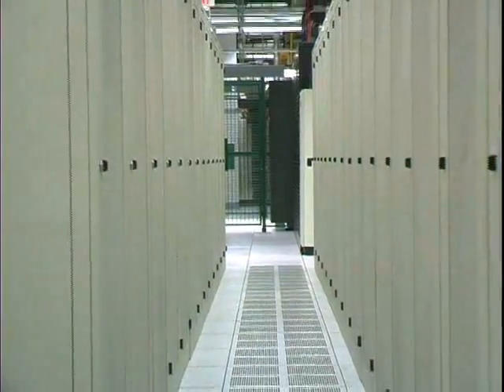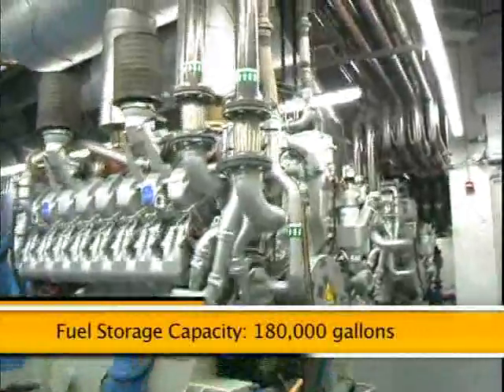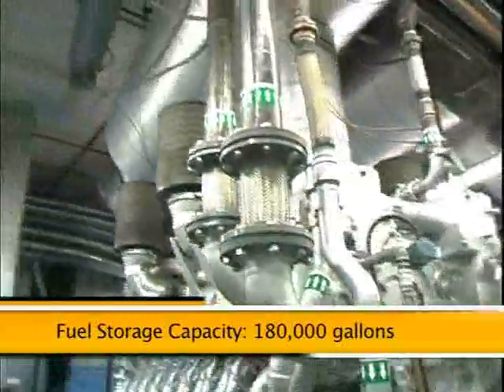Terremark relies on sophisticated backup systems that keep it operational even during catastrophes. On the power side, we get 2 feeds from Florida Power and Light from 2 independent substations, Railway and Miramar, at 13,200 volts, 10 megawatts each. So if we were to lose a substation, we can still power the entire facility through the other one — we're redundant from that capability.